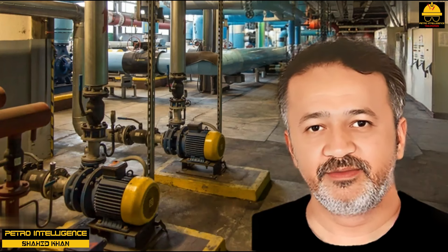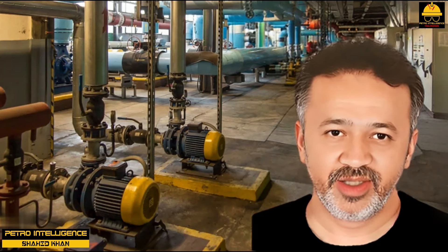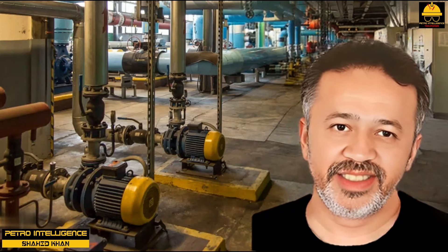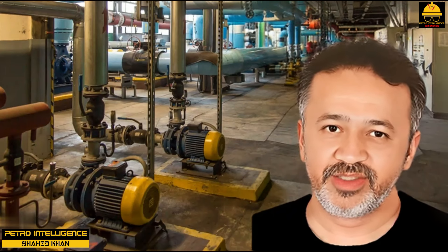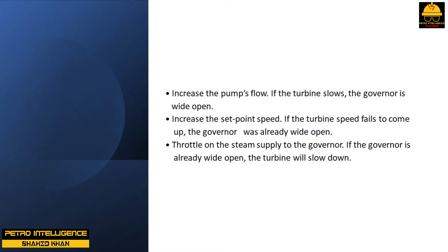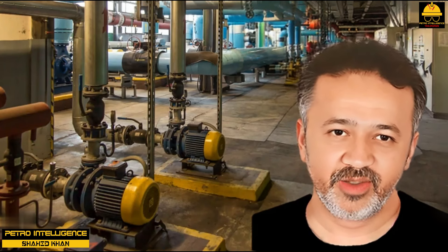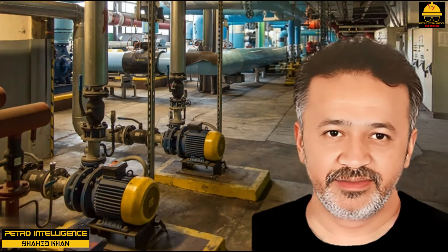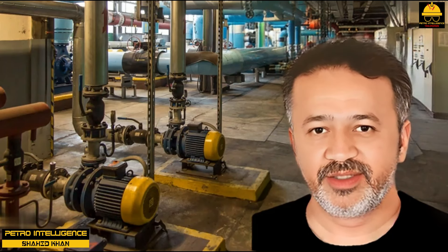A turbine-driven pump is said to be driver limited when the governor's speed control valve is wide open — this valve is usually called the Woodward governor. A few simple methods to determine if the governor is wide open are: increase the pump's flow — if the turbine slows, the governor is wide open; increase the set point speed — if the turbine speed fails to come up, the governor was already wide open; throttle on the steam supply to the governor — if already wide open, the turbine will slow down. Even if the governor steam inlet control valve is 100% open, it may still be possible to increase motive steam into the turbine — the position of the governor when wide open can often be reset to admit more steam flow.